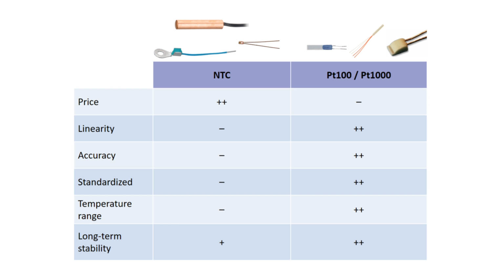PT100 or PT1000 sensors have the advantages that their characteristics meet international standards. Thus, their interchangeability is good. They have good temperature cycle behavior as well as long-term stability. The temperature range is large, from very low temperatures to high temperatures. NTC sensors have the advantage that they are cheaper than platinum sensors and often they are smaller. However, the downside is that NTC sensors are not standardized and therefore interchangeability is limited. Another disadvantage is that the temperature range is not as high as with platinum sensors.